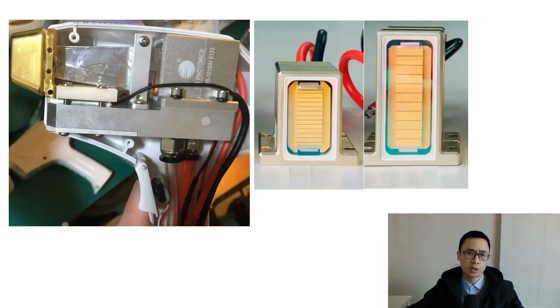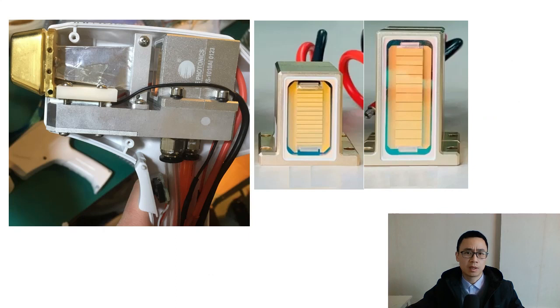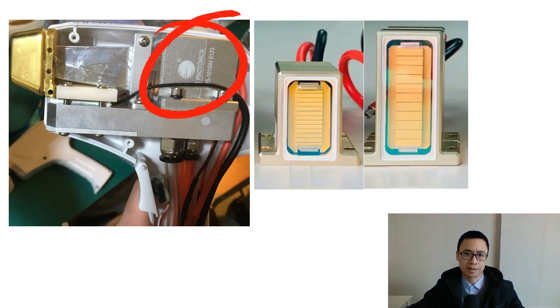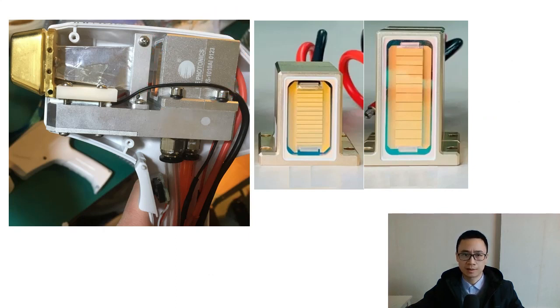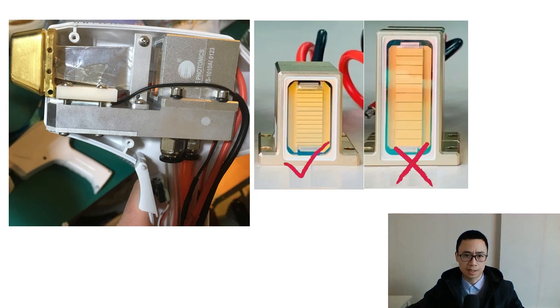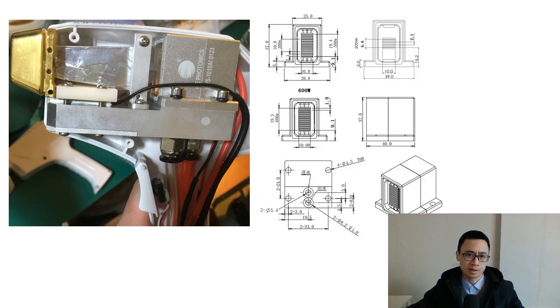If you want to improve the power of the handpiece, you can change the diode laser stack, replace it with a high power laser stack. This should be compatible in size, otherwise it can't be installed into your handpiece.